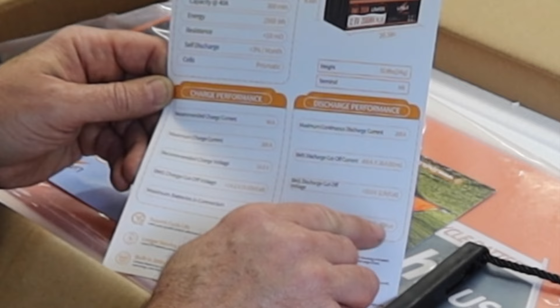So discharge performance, maximum continuous discharge current of 200 amps. BMS discharge cutoff current is 450 amps, plus or minus 20 amps. It says 31 ms. I'm assuming that means 31 milliseconds. And then BMS discharge cutoff voltage is whenever it gets to 10 volts. I'm believing it's saying that it can take it down to 10 volts and then it'll shut off. And then it has a short circuit protection of 200 to 600 microseconds, meaning that if it gets a short, so way less than a second, it'll actually shut itself off. And then the terminals are M8 metric bolts.